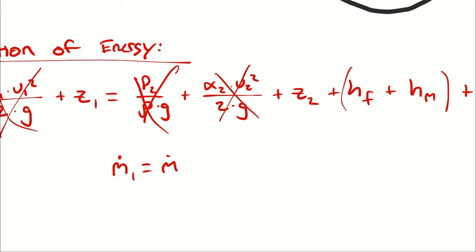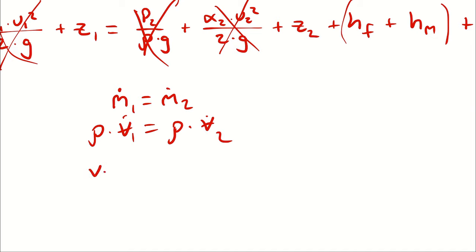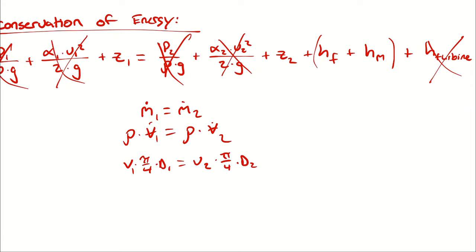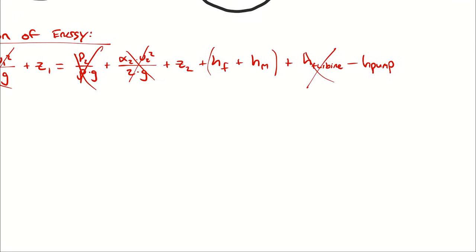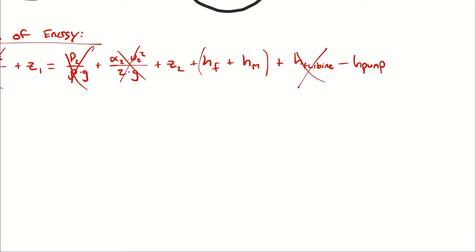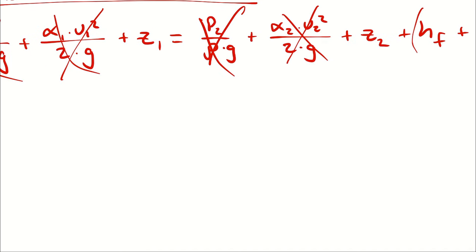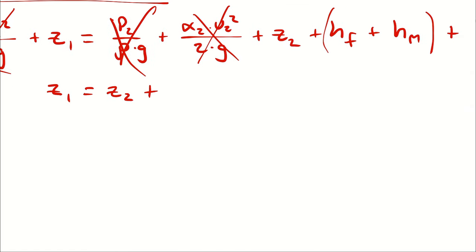If we have steady state analysis, that means mass flow rate at 1 equals mass flow rate at 2 for one inlet and one outlet. Since mass flow rate equals density times volumetric flow rate, and with constant density (incompressible flow), volumetric flow rate at 1 equals volumetric flow rate at 2. Since volumetric flow rate equals average velocity times cross-sectional area, and the cross-sectional area doesn't change, the average velocity must not change. So my simplification gives Z1 equals Z2 plus friction losses (both major and minor) minus the pump head.